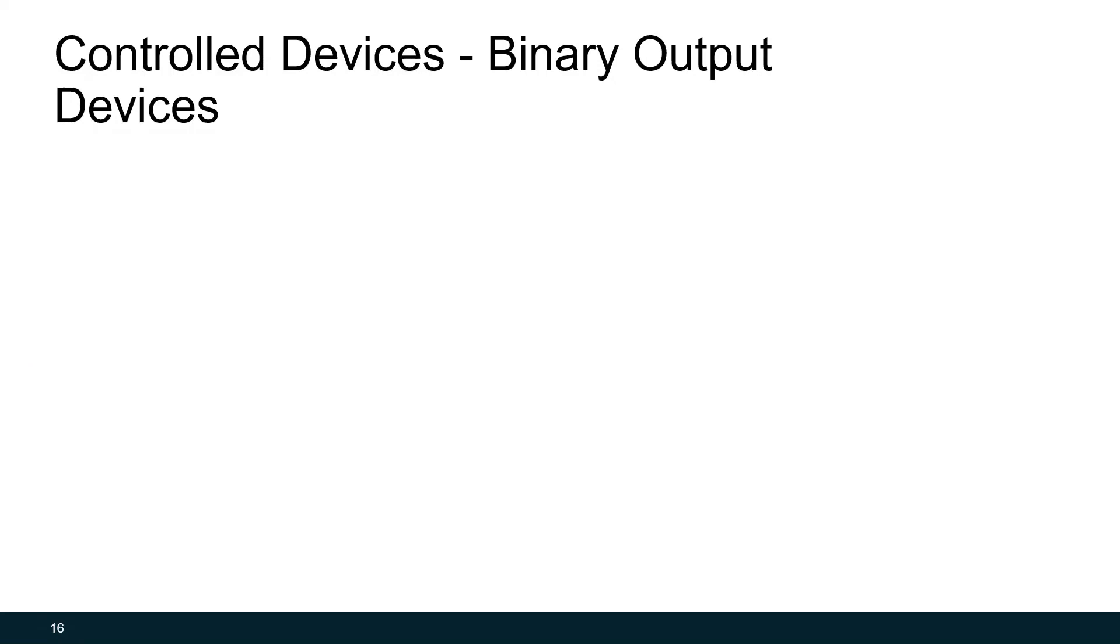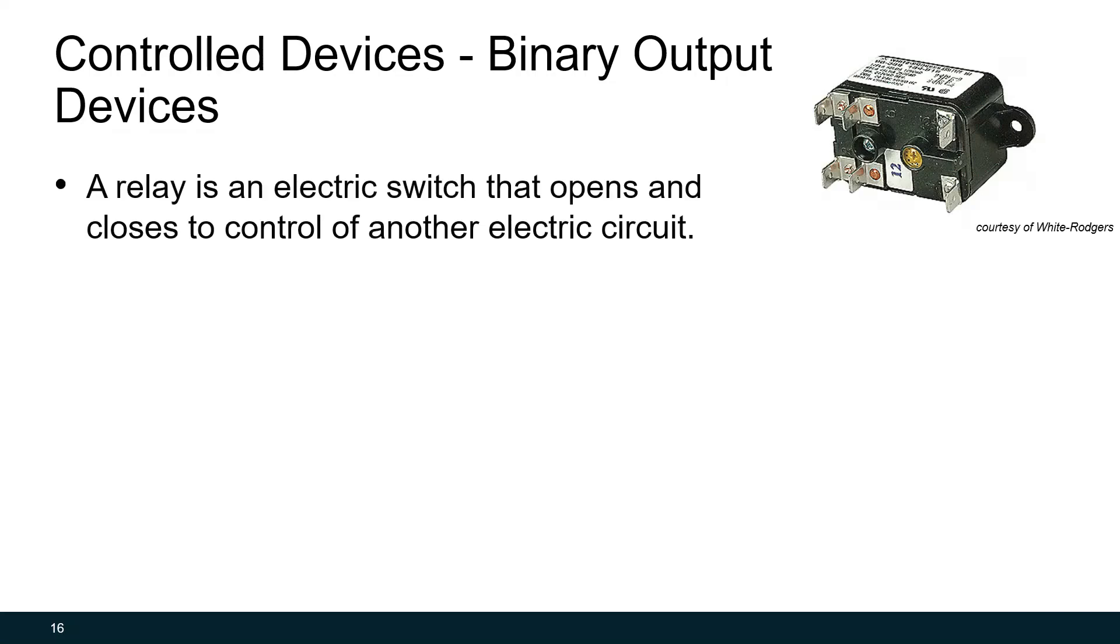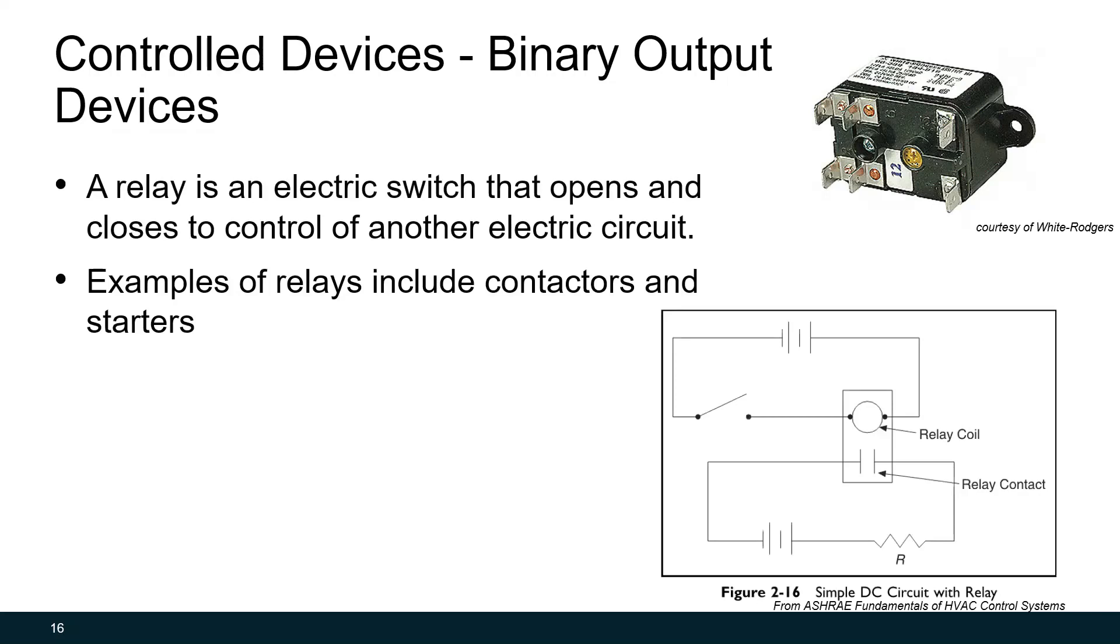We'll now go through a few examples of control devices that are common in the HVAC system. We'll start with binary output devices, and the most common binary output device is the relay. A relay is an electric switch that opens and closes to control another electric circuit. The most common version of these are motor starters, but also other equipment contactors. If you look at the bottom right figure, you'll see we have a relay coil in the top. When this switch closes with a command from the field controller, it will energize this relay coil. When this relay coil is energized, it will close the relay contact, completing the circuit that provides energy to the motor and starting the motor.